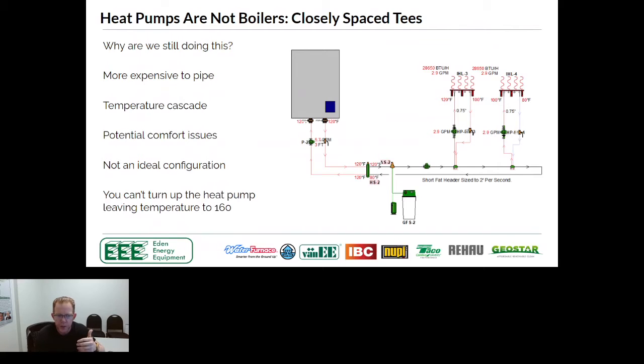But the thing that we need to be aware of is, if you look at this and go, why are we still doing this? If you look at modern methods of doing this with a short fat header, which I'm going to show you in the next session, we're going to go to our live fire air to water lab and actually talk about a system that's installed. And we're actually going to walk through some of the components of it. So closely spaced tees, we have to be aware we've got a temperature cascade. So in this case, I've got 2 sets of closely spaced tees.